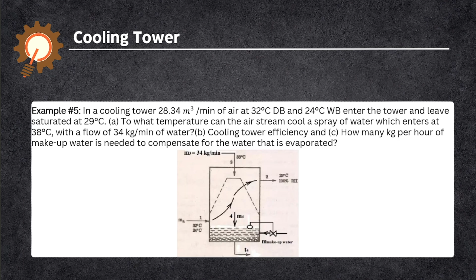So, for point 1, at dry bulb temperature of 32 degrees Celsius and wet bulb temperature of 24 degrees Celsius, makuha natin yung ating enthalpy number 1, which is equivalent to 72 kilojoules per kilogram, and ang ating specific humidity number 1 na equal sa 0.0156 kg per kilogram, and ang ating specific volume number 1 na equal sa 0.884 cubic meter per kilogram. So, to solve for mass ng air, ang gagamitin natin dyan is ang ating volume flow rate all over specific volume number 1. So, by substitution, 28.34 cubic meter per minute all over 0.884 cubic meter per kilogram is equals to 32.06 kg per minute.